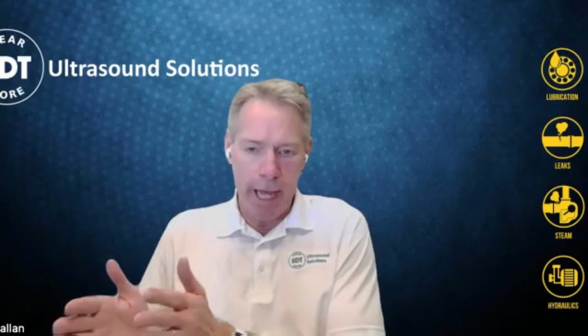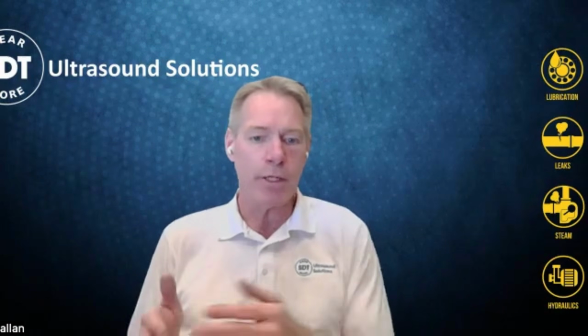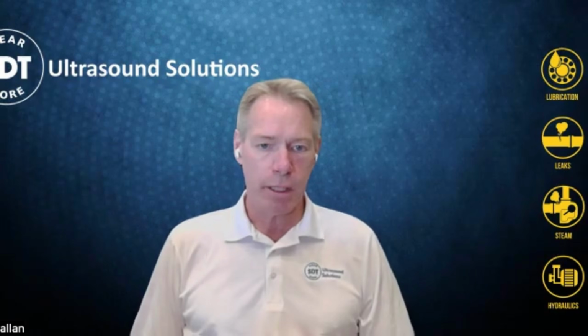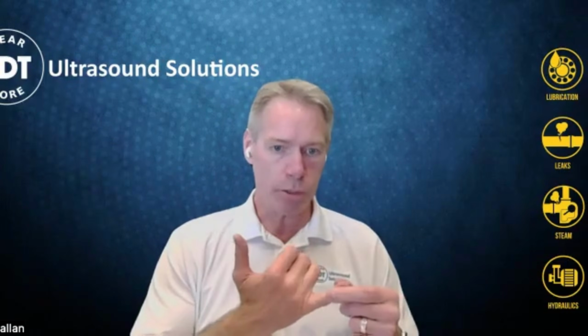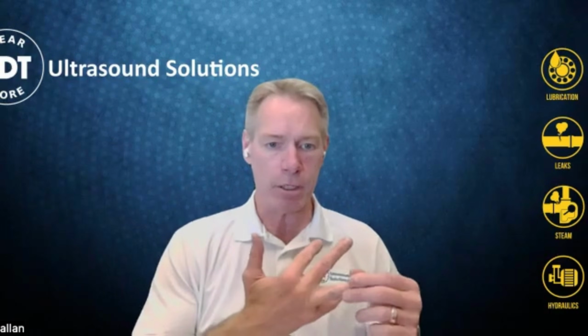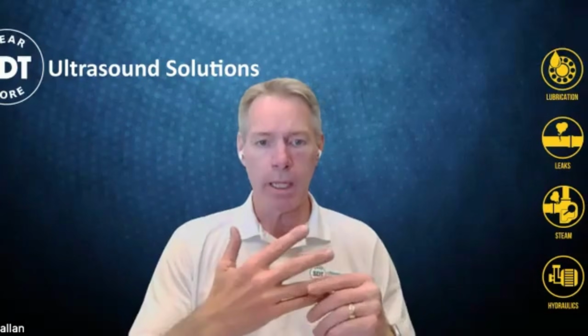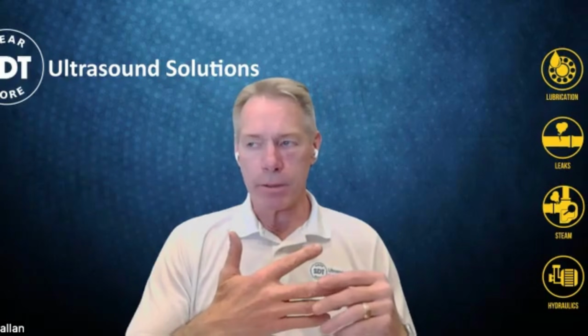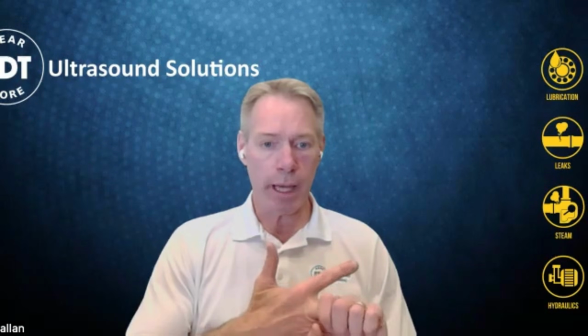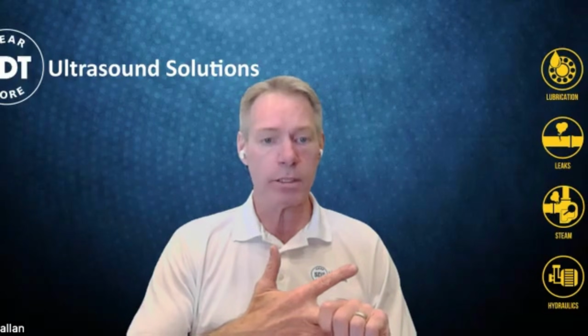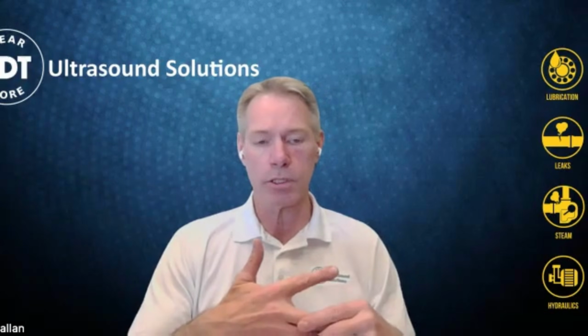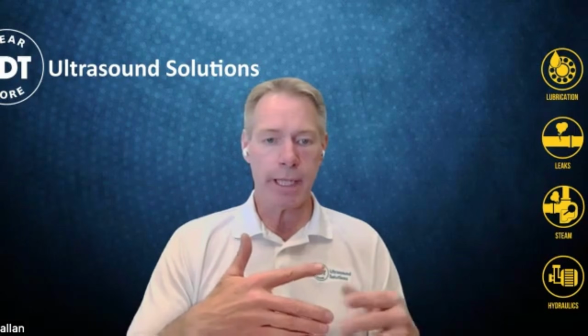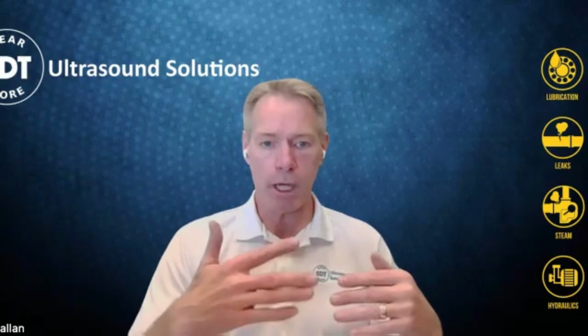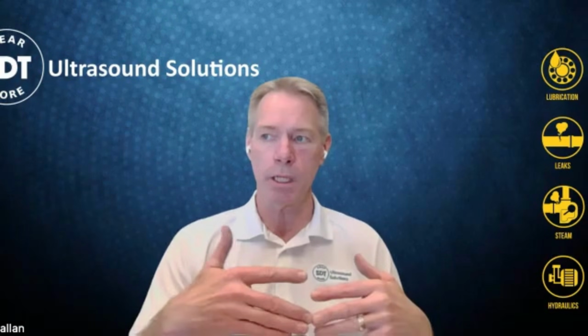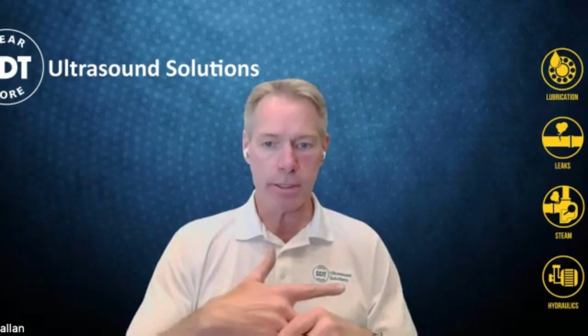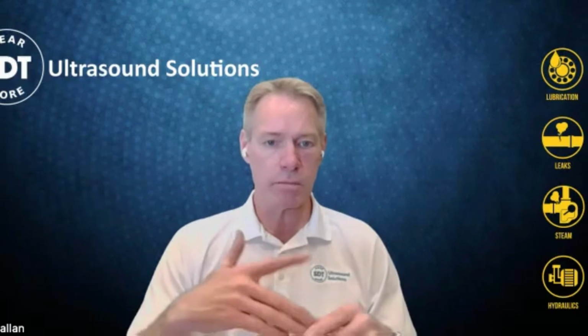But what we did is we categorized those hundreds of applications down into what we call the 8 application pillars. And they are lubrication, which we've talked about. Then we say mechanical, which is the sliding and the rotating. Then we talk about electrical. So when you have issues with insulation material, you get surface partial discharge. The ultrasound is very good at detecting partial discharge on medium and high voltage. Could be switchgear cabinets, could be transmission distribution lines, anything in the substations, bird caging and some cabling.